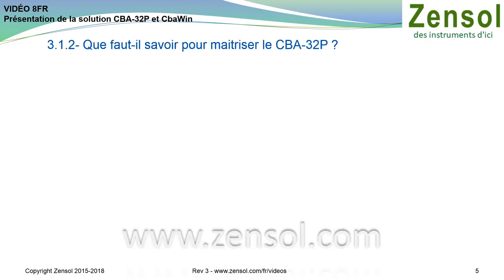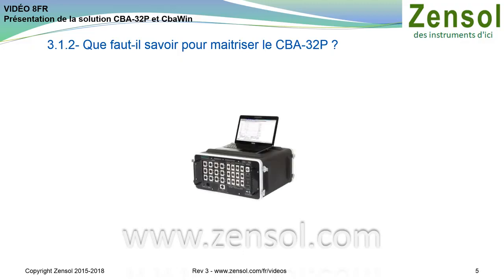What do you need to know to master the CBA-32P? Although the CBA-32P is dedicated to circuit breaker diagnostics, it is above all a universal recorder with 2 relays, which, for example, triggers opening and closing operations in circuit breakers. As described in this slide, the CBA-32P is at the heart of the recording of all kinds of electrical signals, typically found in circuit breakers and their control cabinets.